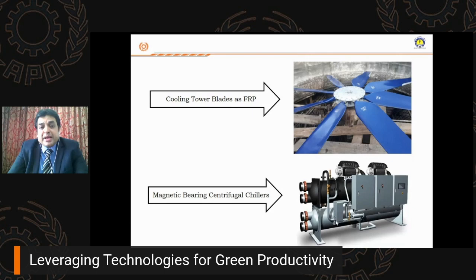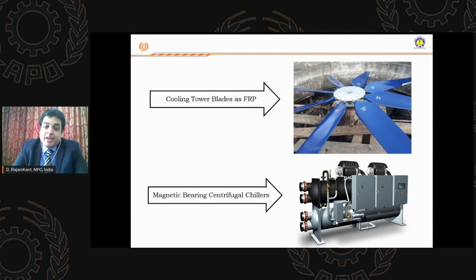You have these magnetic bearing centrifugal chillers, oil free. You have a permanent magnet, where because of this magnetic field this chiller operates, and this is one new technology which all the hotels are implementing. All these chillers are coming in all the hotels. The capex is slightly higher, but if you see the overall return on investment, because it is maintenance free, it has been implemented in all these hotels now.